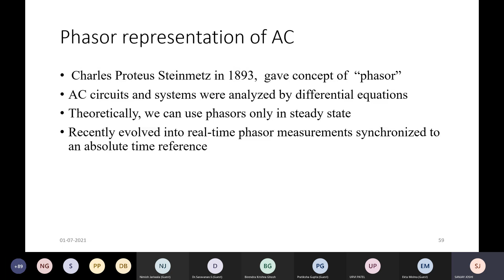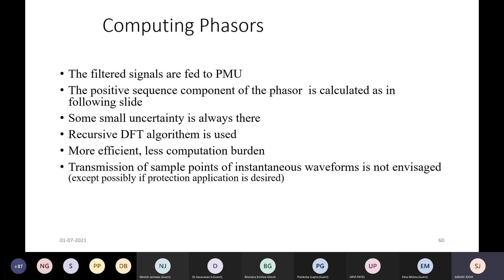How to compute phasors? Filtered signals are fed to the PMU. The positive sequence component of the phasor is calculated. A small offset is always there, but the recursive DFT algorithm is used, which is more efficient and has lesser computation burden.